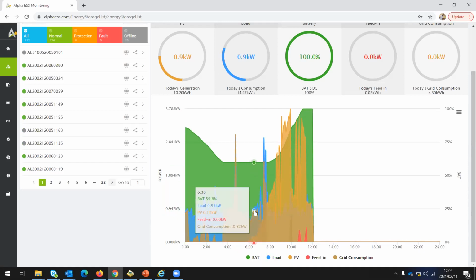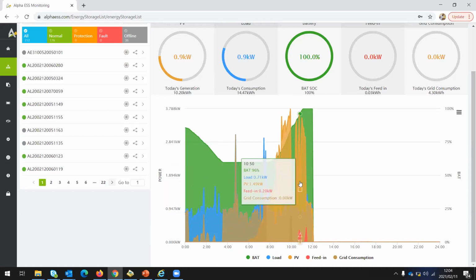But as soon as the PV came up, the grid power started dropping because some of the power was now being supplied by the PV. As I have said, the system operation first uses your PV to supply your loads. Once all your loads have been catered for, from there it charges your battery. Once the battery is catered for, then it feeds into the grid. So when PV started rising around towards 8, the PV power was quite high. It was able to supply the loads, none of the grid was being used, and the excess was used to charge the battery. You can actually see the battery SOC rising until around 11:10.